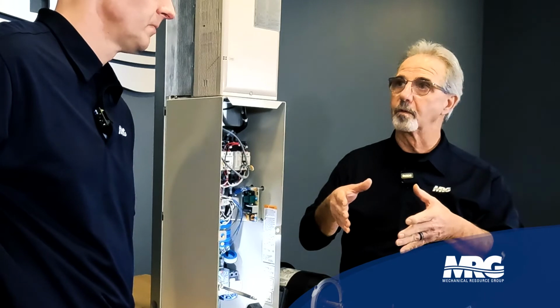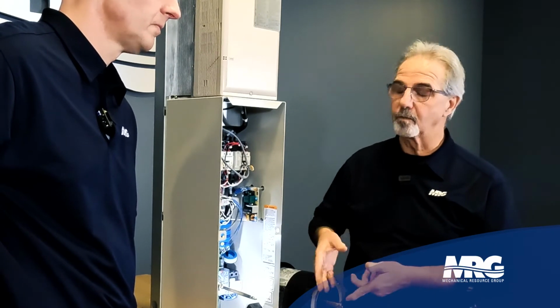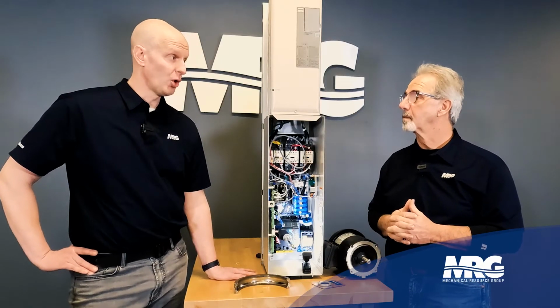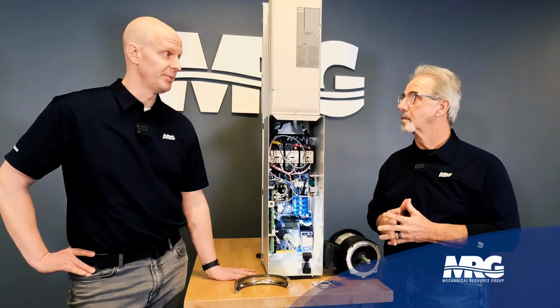And you got to be fairly skilled. Yeah. Because you got to make sure you put them in there the right way. You got to make sure you get them on a shaft, and you got to make sure the surface is clean, because that was one of the other drawbacks: if where the brush rides, if your housekeeping isn't all that great, anything that gets in there and insulates that shaft, you lose the ability to give it a ground path. So it had some drawbacks. So cost-wise, I'd say that this is fractional compared to other methods that we've used in the past. A cost-effective, permanent solution to prevent premature bearing failures.